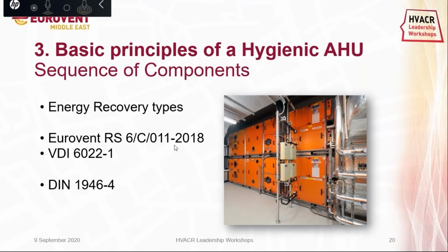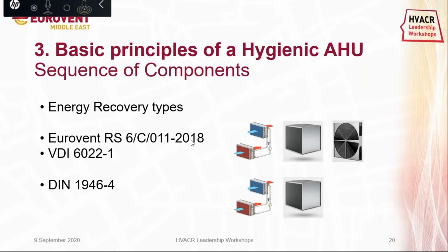Yeah, an example of a handling unit with a runaround heat exchanger. And yeah, Eurovent and VDI, they also allow the rotary wheel as well. But again, if some conditions are fulfilled, as explained before, it's mostly related to the permitted level of EATR, the exhaust air transfer ratio. And also the rotary wheel shall always have a properly dimensioned purging sector, otherwise it's too risky and not allowed for a hygienic air handling unit.